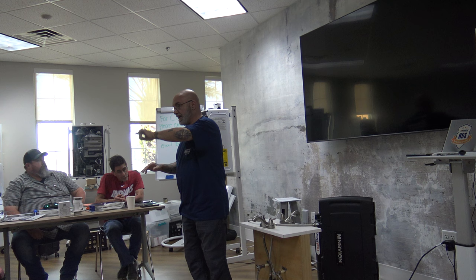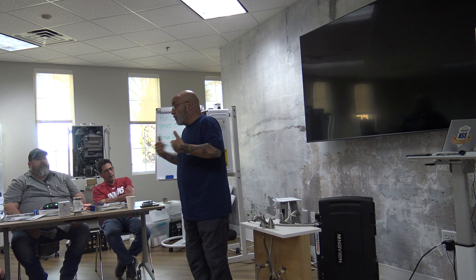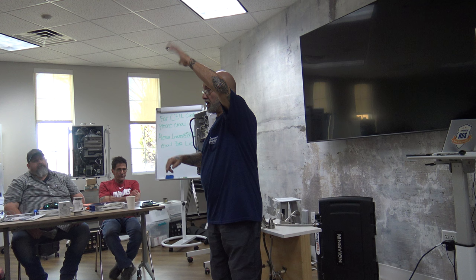You come up with your candy cane, we paint it black. For those of you that don't like to go on a roof, if you do, you could do it. If not, we use a roofer, especially since we have a lot of tiled roofs. So we just go right up. We take the B vent out, and then we just go right up with the 2-inch, support it like it's a vent stack from a plumbing system, but we make our candy cane and we come up about 20 inches above the roof. And we paint it black so it's unobtrusive. So that is the number one problem that we see.